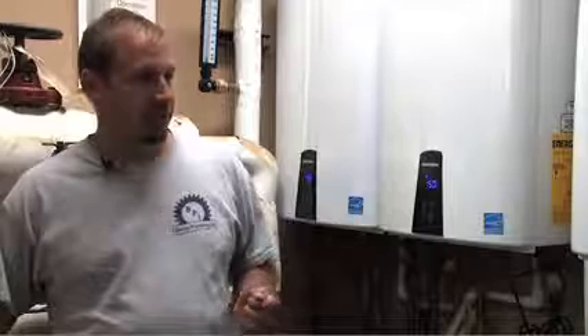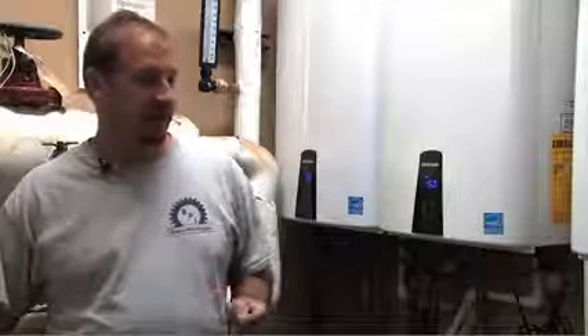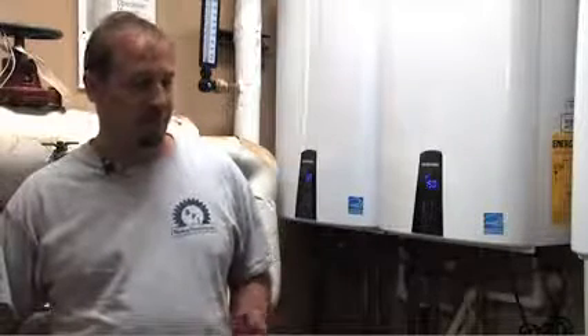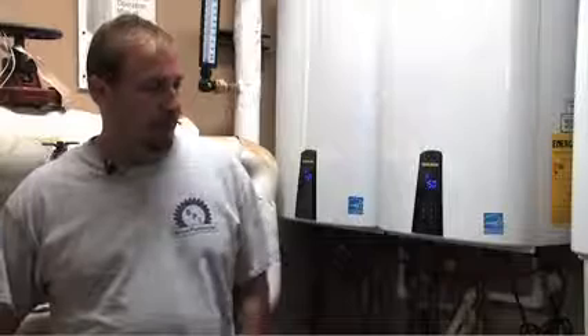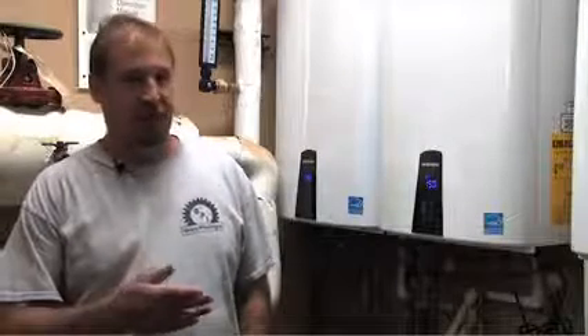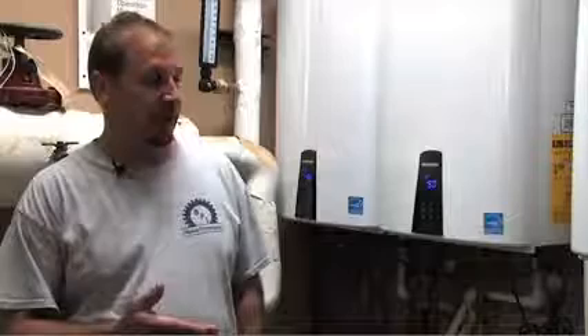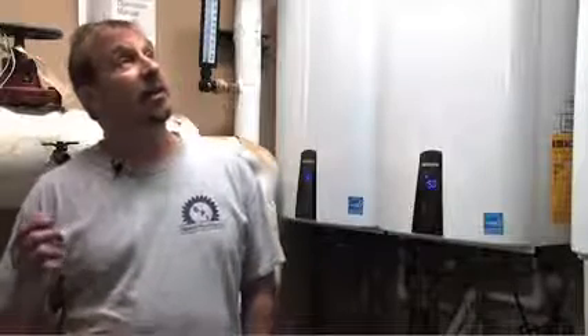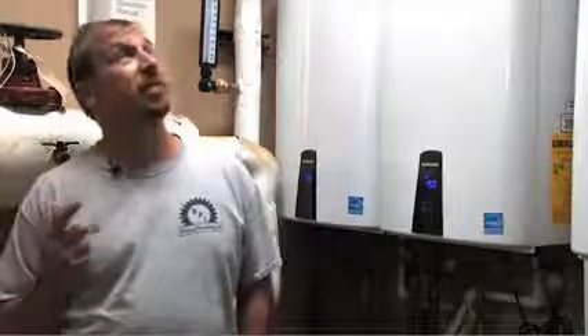We did cascade these units, and the cascading actually works nice. I've done other brands, and this is the best way to install these from what I've seen. It allows each one to work on an equal pressure basis. We did cascade the vents also. I had existing vents here, so there were 2 inlet and 2 exhaust. So by putting 4 in, we cascaded 2 to each inlet and exhaust. So we knew we had plenty of venting.